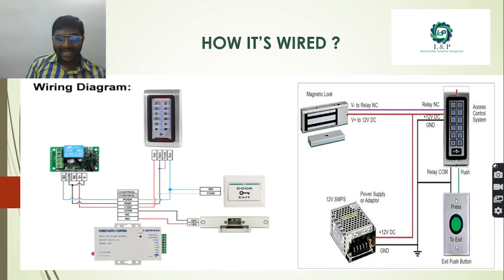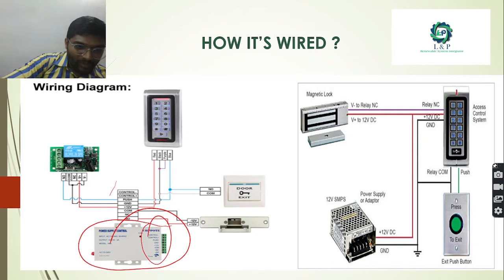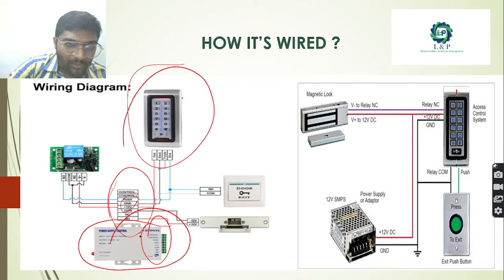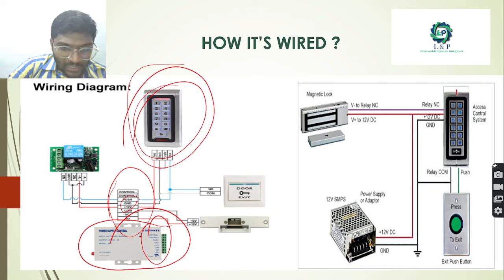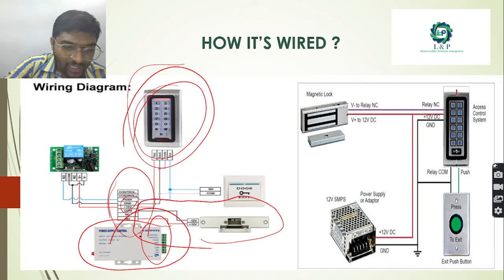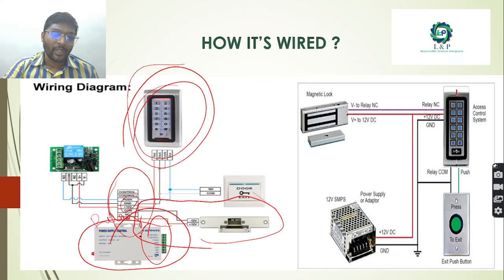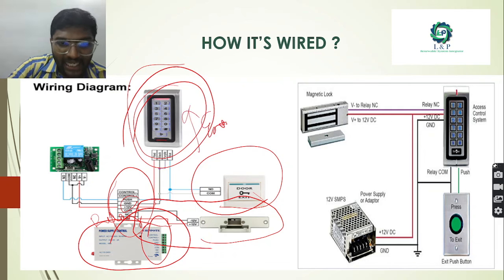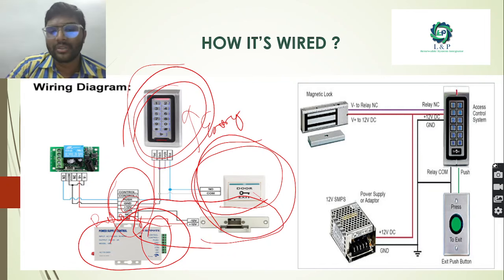This is a very simple wiring diagram. For a simple application, we have a power supply. The card reader has four terminals. Connections include push connection, ground, and a 12 volt supply. For the lock to work properly, we connect it with either NO or NC relays present inside the controller. Through the 12 volt power supply, we control the locks. Exit push buttons and switches inside the room can also be used to exit.